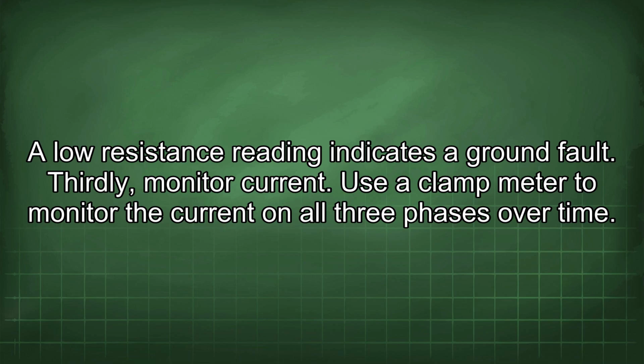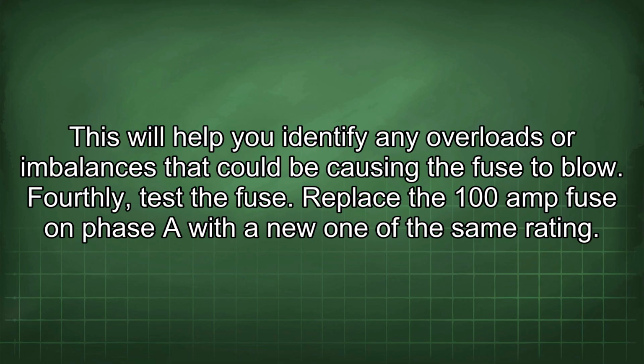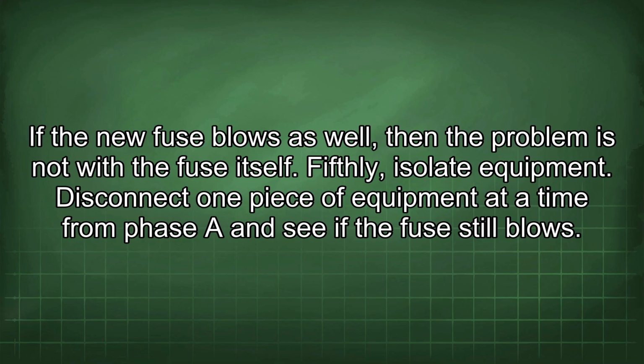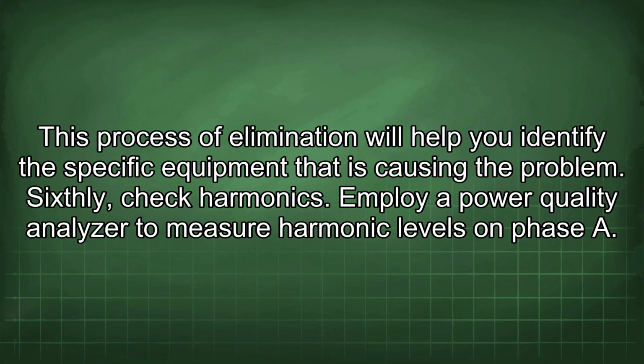Thirdly, monitor current. Use a clamp meter to monitor the current on all three phases over time. This will help you identify any overloads or imbalances that could be causing the fuse to blow. Fourthly, test the fuse. Replace the 100 amp fuse on phase A with a new one of the same rating. If the new fuse blows as well, then the problem is not with the fuse itself. Fifthly, isolate equipment. Disconnect one piece of equipment at a time from phase A and see if the fuse still blows. This process of elimination will help you identify the specific equipment that is causing the problem.